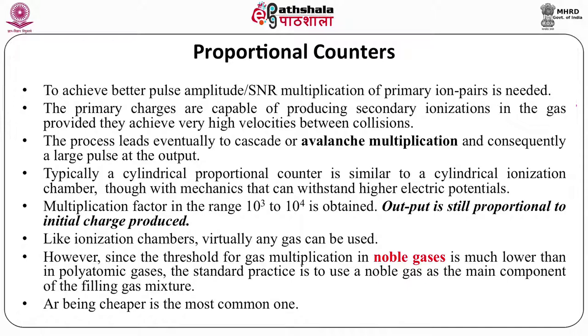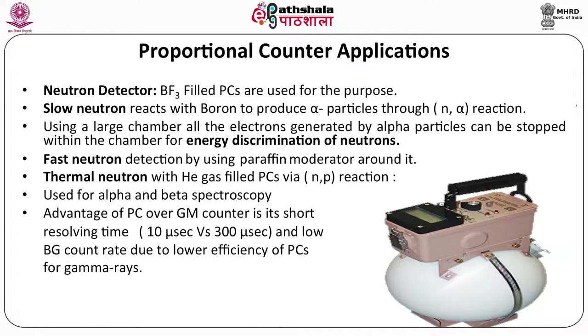The output in terms of charge or current is still proportional to the initial charge produced. Like ion chambers, virtually any gas can be used; however, since the threshold of gas multiplication in noble gases is much lower than in polyatomic gases, standard practice is to use a noble gas as the main component of the filling gas mixture. Argon, being cheaper, is the most common gas used in proportional counters.